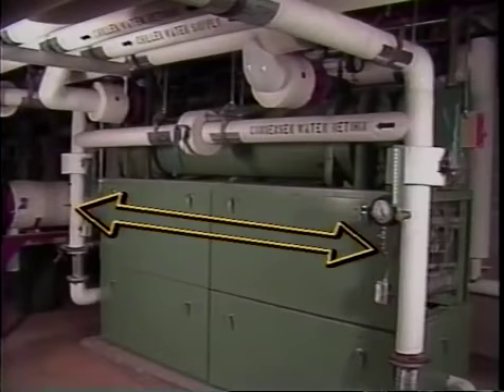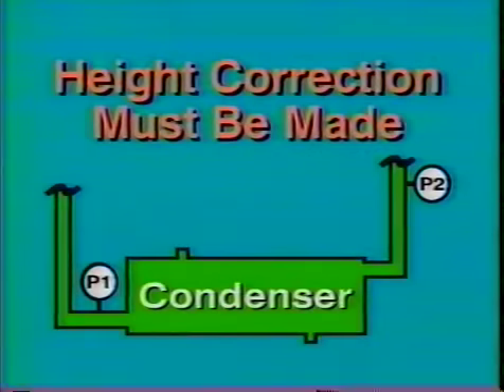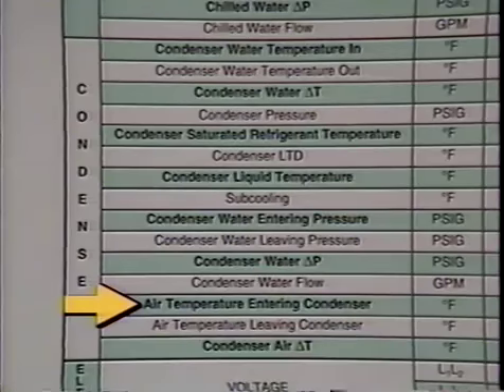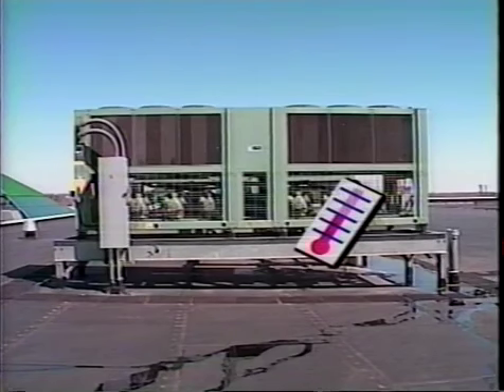Pressure taps for taking pressure readings across the condenser should be as close to the inlet and outlet as possible and at the same height. If there is any difference in the height of the gauges, a correction will have to be made. We'll discuss this in more detail later in the program. Air temperature entering condenser. Measure and record the outdoor ambient air temperature entering the condenser. This is a very important factor on air-cooled condensers because it provides a reference to what the condenser saturated refrigerant temperature operating conditions should be.